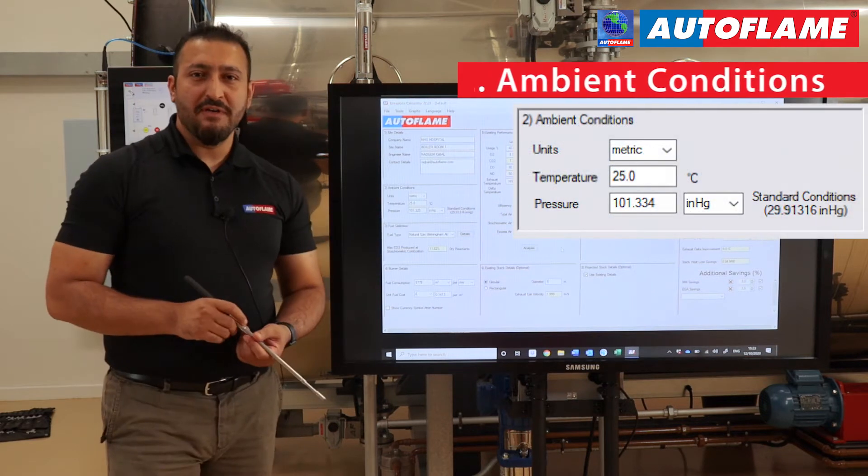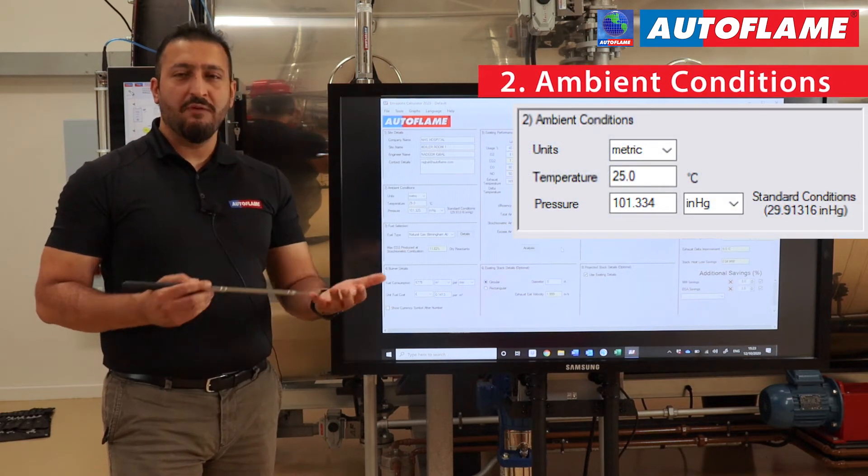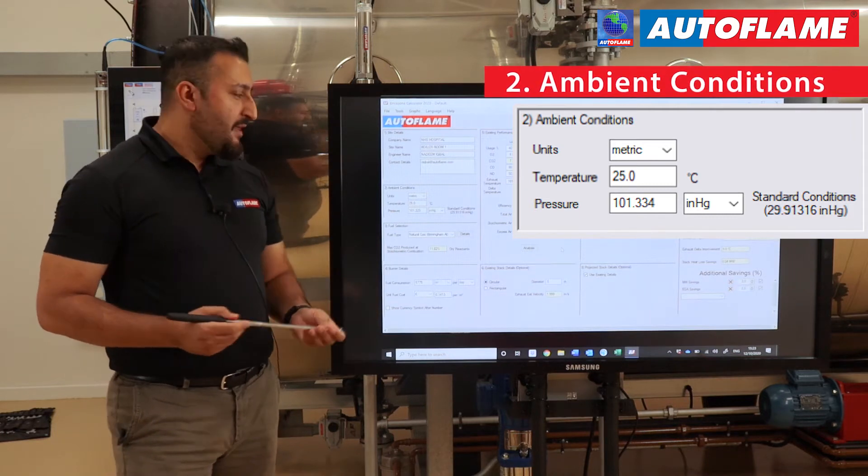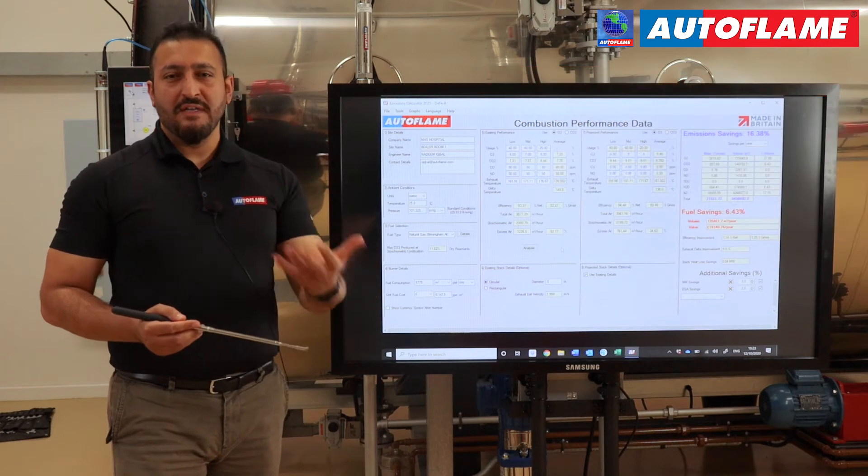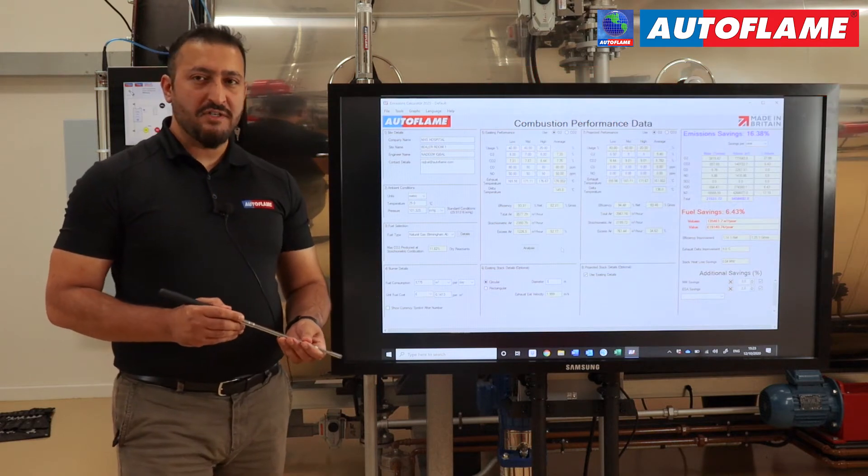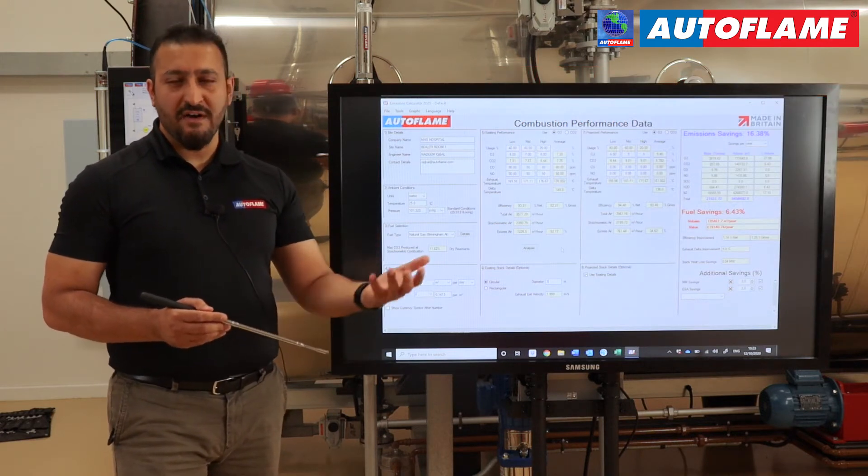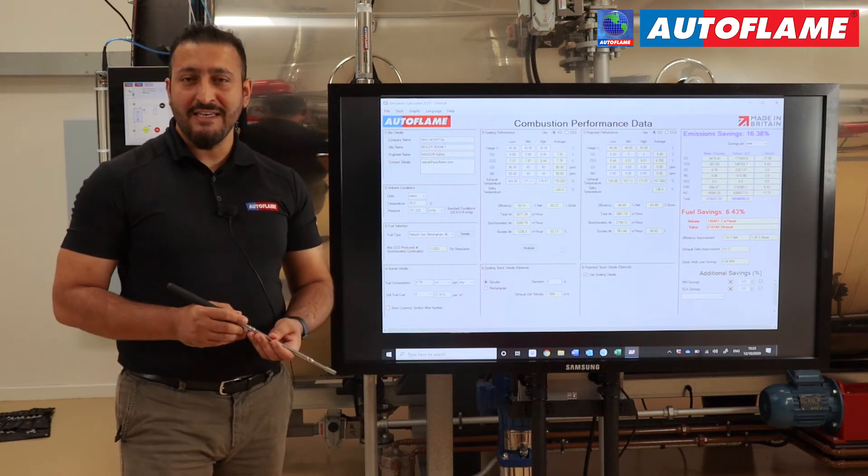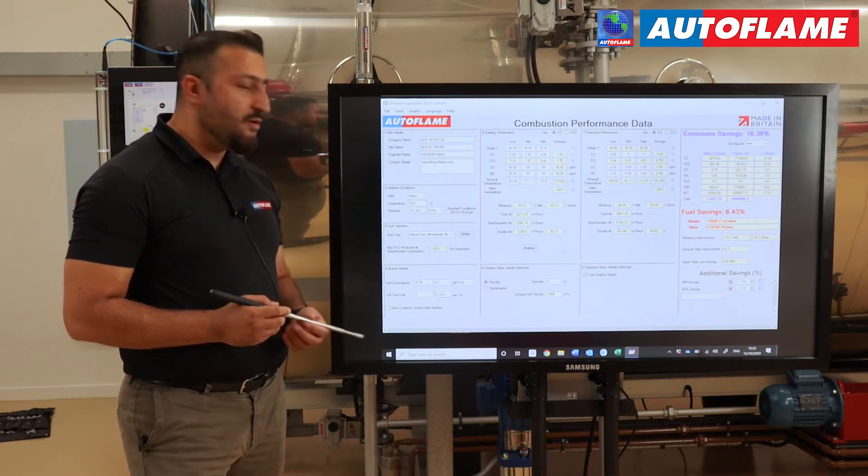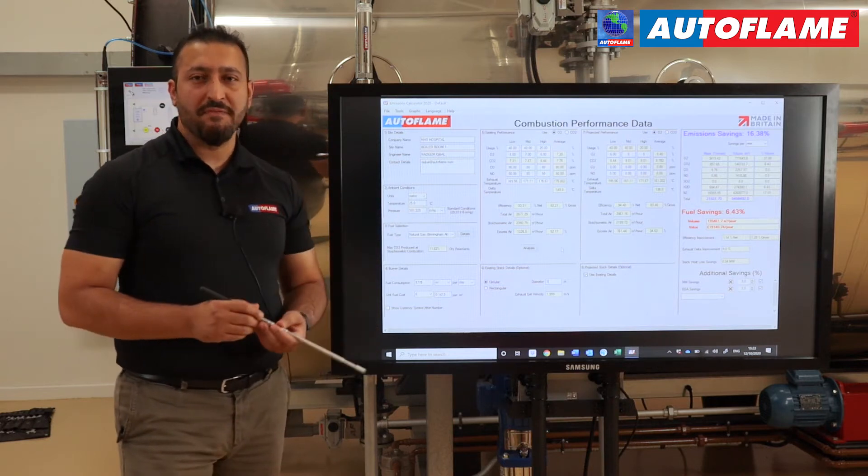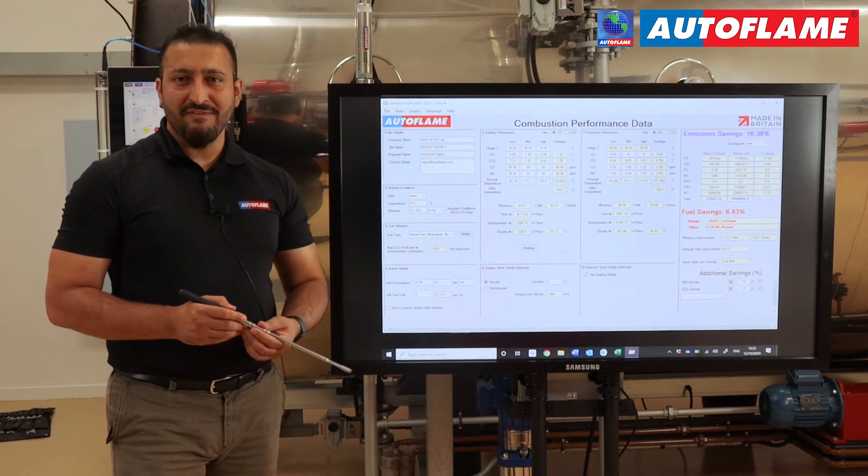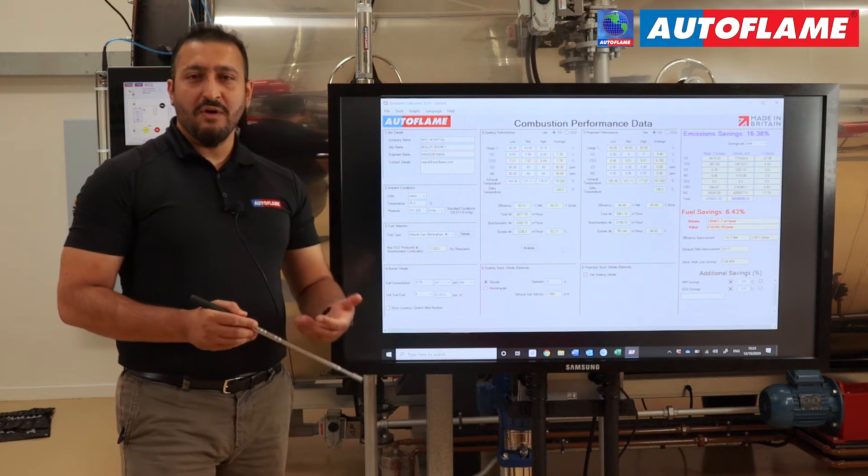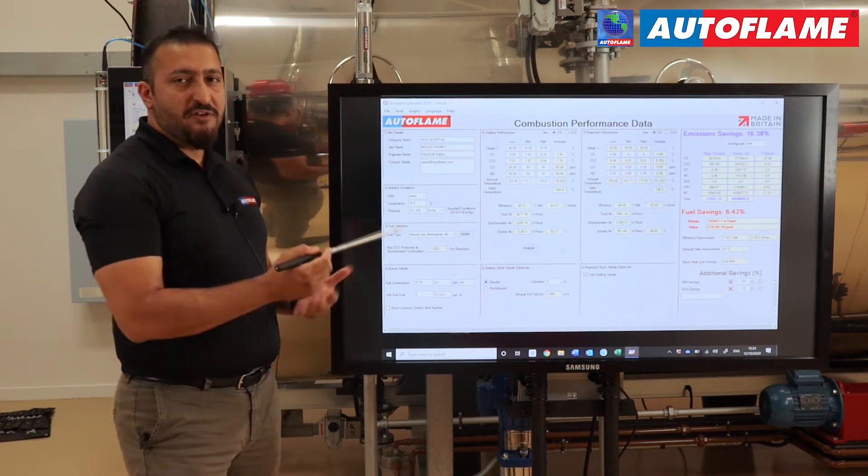Section two, that's where we put the ambient conditions. Are we measuring in imperial or metric units based on where you're located? Then we need the temperatures. Obviously your ambient temperatures can affect your combustion. The colder it is, the harder it is to make the savings. The warmer it is, the fuel and air mix is quite easy. So we need to know this information. Also your ambient pressures. If you are at sea level, then the ambient pressure will be taken as the standard 1.01. If you are on high altitudes, then this value will be slightly lower.